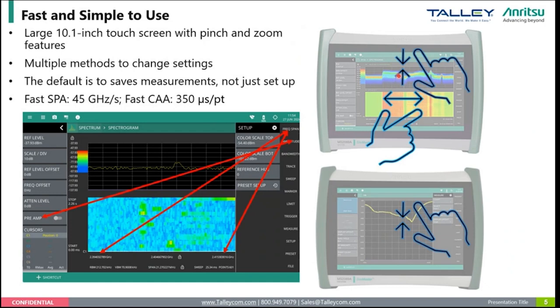On top of that, there are multiple ways for you to change the settings. As you can see here, we have the traditional buttons, but we also have additional cards here, which you can press and change. In this case, you can change the amplitude or the frequency. Besides changing frequency here, you can just tap here and change the frequency as well. Of course, you have the ability to lock this if you don't want it to be touched while you're moving the instrument around. In addition, we've made sure to default, when you get the instrument straight from the factory, that when you save your measurement, you're saving everything, not just the setup. Because we've heard customers say multiple times that they come in, they hit save, save, save.